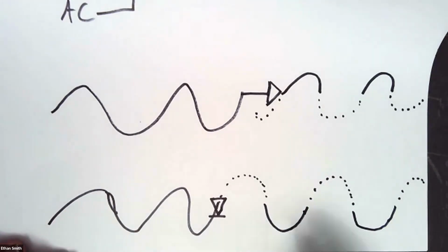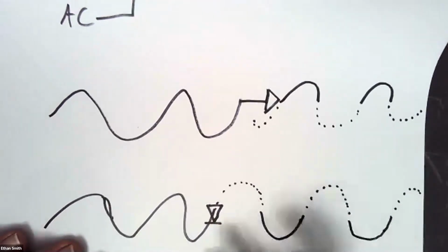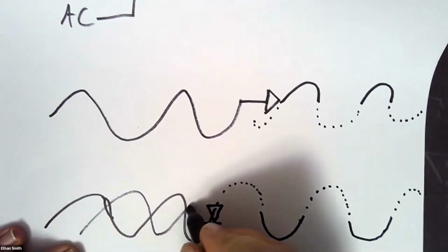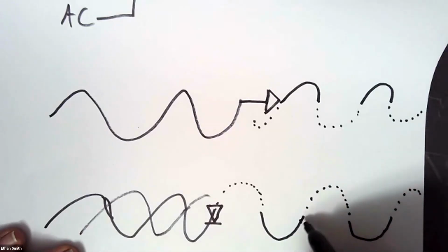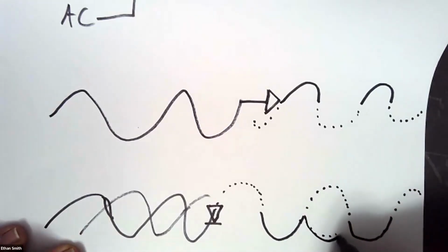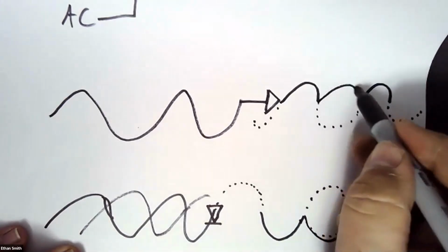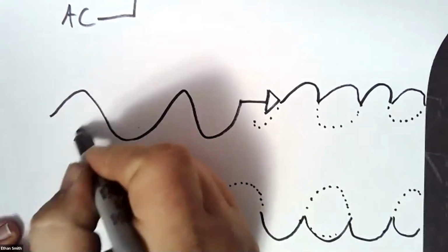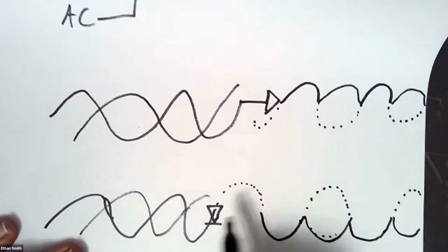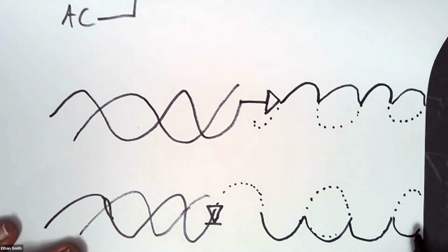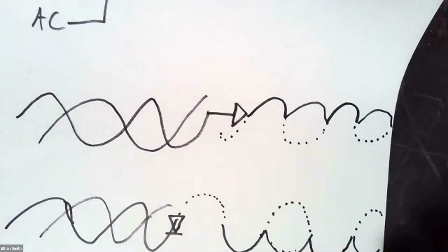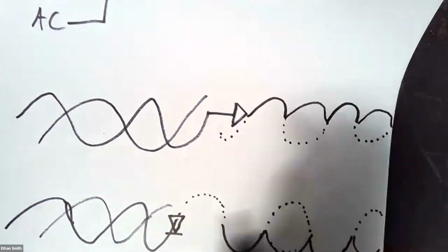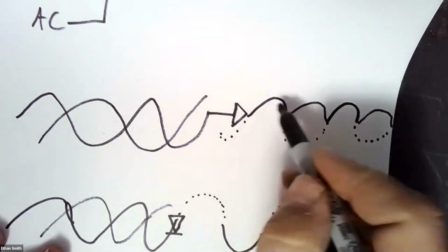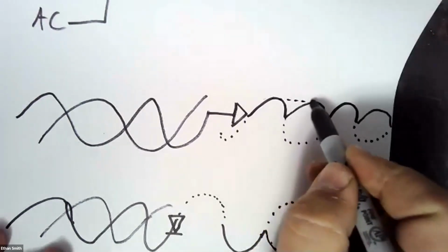What Mitsubishi does in this is they take multiple phases. They're running 2-phase power, so 100 or 240 volts, and they end up with 2 phases that they've chopped on either side. So they end up with a positive DC signal and a negative DC signal. What we can do is take those DC signals and make it smoother. Mitsubishi runs it through a big smoothing circuit with a bunch of capacitors, so instead of having a pulse DC, it smooths that out a little bit.